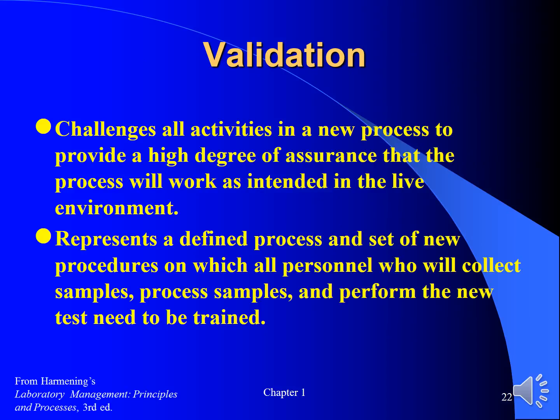To ensure that new processes will work as intended, they are required to be validated before being put into use. Validating the new testing process ensures that it will perform as expected with the laboratory's workflow, instrumentation, personnel, written procedures, and information systems. Training needs to be documented, and personnel competence in the new process and procedures needs to be verified before the new test is implemented in the live environment.